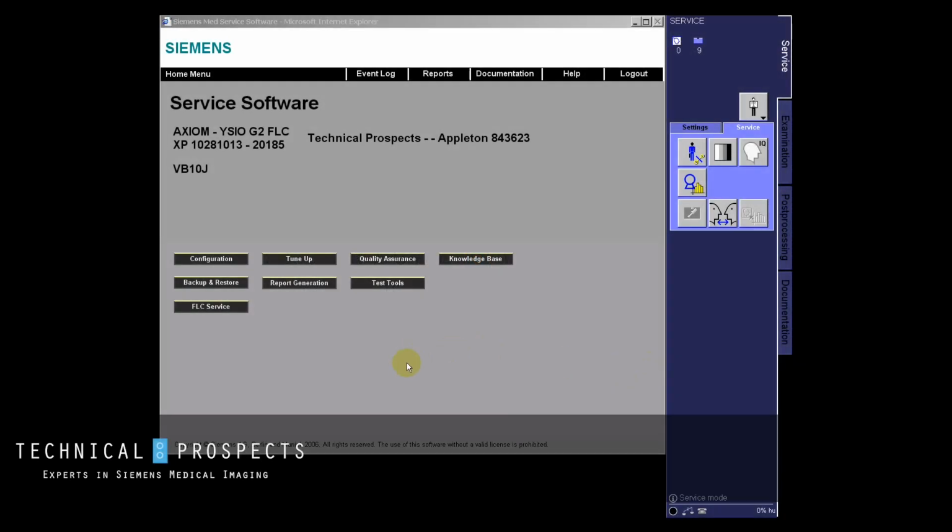Today we're going to talk about checking your WLAN settings prior to doing any replacement or service work on a Siemens Ysio room, this one is, regarding the portable detector. So where you check and verify your WLAN settings is in the service platform here.